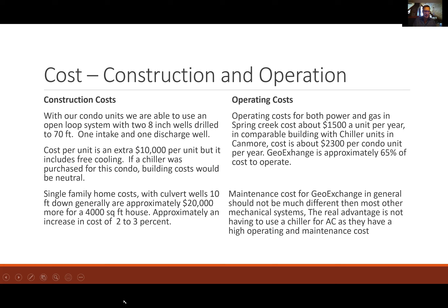They will need maintenance. They will need to be replaced in 15, 20 years, just like boilers do. You do need to maintain your exchangers, but the real advantage is you don't have that chiller. We have free cooling in Spring Creek. We're groundwater straight to exchanger, and the groundwater goes right back into the ground. We don't have a big chiller unit that we have to maintain and operate. So that's a huge benefit on the air conditioning side. That's Spring Creek, and that's how efficient we believe it's been for us.